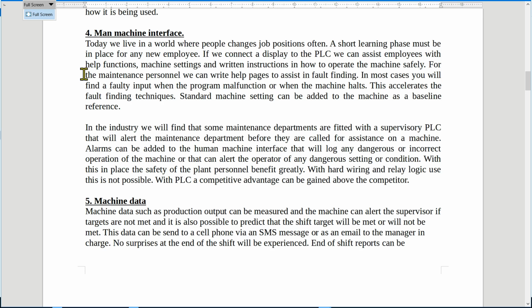For the maintenance personnel, on the other hand, we can write help pages to assist in the fault finding. In most cases, you will find a faulty input when the program malfunctions or when the machine halts. Now, the use of man-machine interface accelerates the fault-finding techniques considerably, and standard machine settings for the operator can be added to the machine as a baseline reference. And in today's world, it is much easier to interface the man to the machine, where both of them can communicate in helping each other.